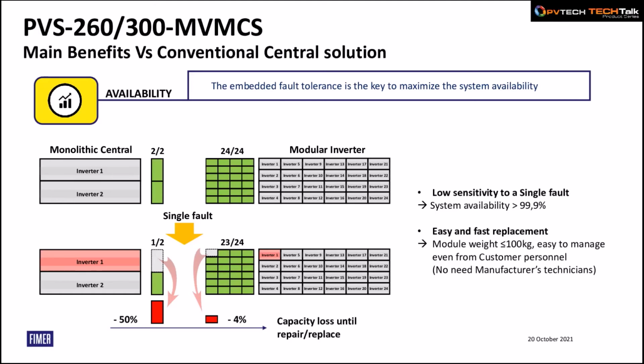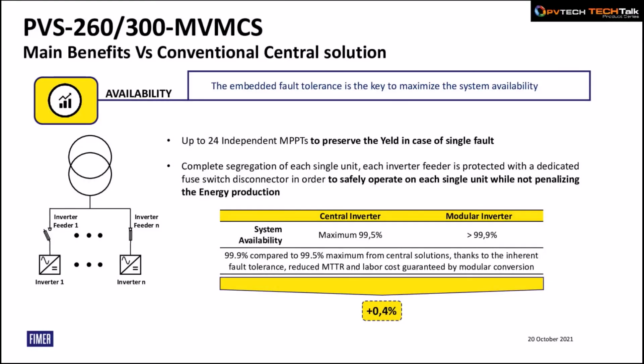We are also reducing the mean time to repair, thanks to the light weight of each power conversion module, less than 100 kilogram. So it's easy to manage even for customer personnel. That won't be possible without complete segregation of each single building block. Each unit is individually protected, so that in case of a failure, the failure does not generate a sort of domino effect. So all units are individually protected to prevent a single point of failure from adversely affecting the rest of the system.